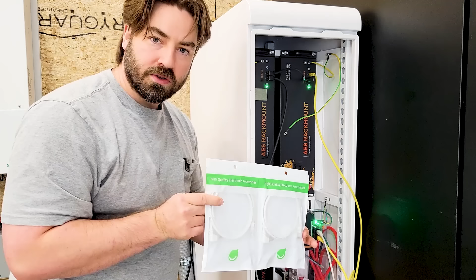Now we're a bit further in the future. I've actually been running this for a while, running the house, and the batteries have been working fantastic. I got the new Cat 6 wires, so let's put them in and then we'll be able to get the door on this thing. If you remember, I had to run my own Cat 5 wire from the uppermost battery down to this switchboard, which lets us turn off all the batteries. It also has another function: you can wire this up to an external remote cutoff switch, a momentary switch, to kill the batteries from outside the building. Pretty cool. But I had to run my own wire, so I ordered some new Cat 6 wire with the correct 90-degree fitting. It's a pair, and I'll leave a link in the description.